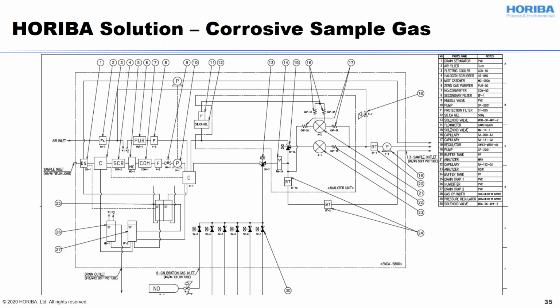Here is the flow schematic for the ENDA-5000 series. As you can see, here is the drain separator and the cooler unit, and also another cooler unit right here. So these three-step cooler units are dehumidifying the moisture out, and the scrubber and NOx scrubber in the mist catcher will capture the unwanted components such as SO3 or HF and HCl, stuff like that.